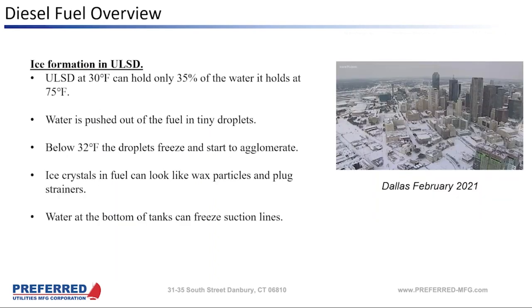So another big thing is ice formation in ultra low sulfur diesel, and I experienced this firsthand in 2021. Ultra low sulfur diesel at 30 degrees F, well above its cloud point, only holds about 35% of the water it holds at 75 degrees F, which means if your diesel gets chilled from 75 F to 30 degrees F in cold weather, it's not going to be able to hold as much water as it did before, and the water is going to drop out and go to the bottom of the tank, and it can potentially freeze at the bottom of the tank, and that's where your suction pipes terminate, at the bottom of the tank.